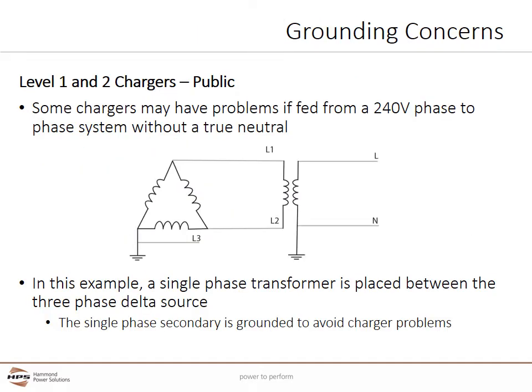Let's talk about grounding concerns. There is some concern that vehicle onboard chargers may have problems if fed with a 240 volt phase-to-phase system without a true neutral. In this example, a single-phase transformer to the right of the delta system is placed between the three-phase delta source and the charger. The single-phase secondary is grounded to avoid charger problems.